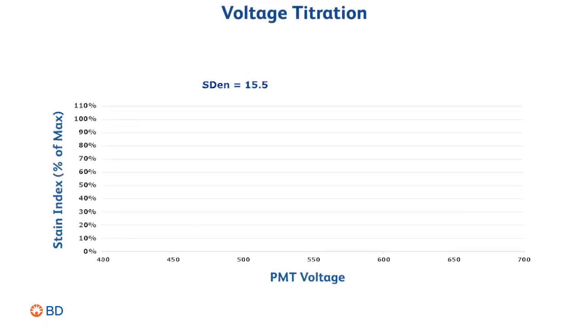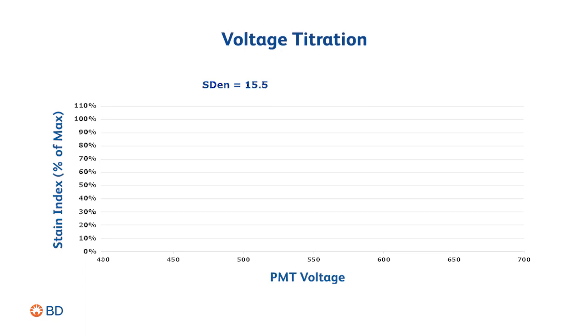If you don't know the electronic noise, you can still optimize your detector to maximize resolution by performing what is called a voltage titration. To do this, run a sample such as anti-CD4 stained cells or capture beads at different voltages and calculate the stain index at each voltage. The goal is to use the lowest PMT voltage that will maximize the stain index. Above this PMT setting, there is no improvement in the stain index.